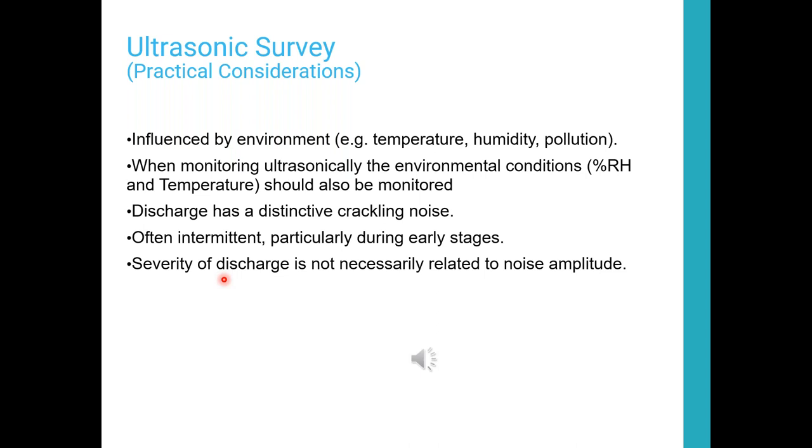Especially with the ultrasonic, if it changes with humidity, it's going to be partial discharge. Other things emit ultrasonic noise: bearings, blower motors, a lot of things create ultrasonic noise. There are certain characteristics we look for in PD, and one of them is changing with humidity. So if you have high activity one day and you go back and it's down and the humidity is down, and you've noted your humidity and you see it trending that way, it gives you more information supporting the fact that it's surface discharge. So noting your environment, your temperature, your humidity helps.